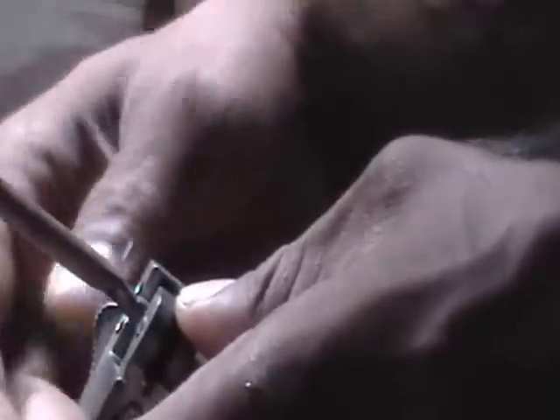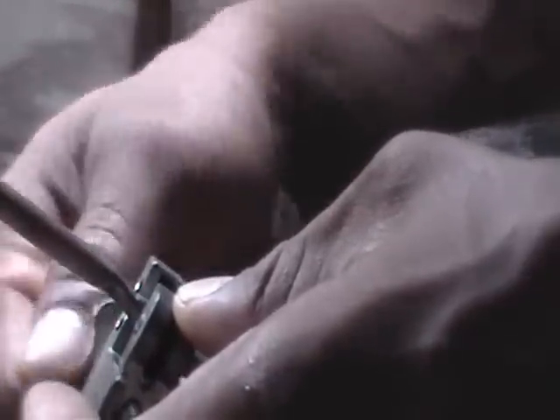The first order of the day is to cut this pipe right at that kink. I have my tube cutter — I'm going to place it around the line. You just want to grip it just slightly. As you turn, you just tighten. What is happening is this blade is just going deeper and deeper in — as I tighten and I turn, it's sinking deeper and deeper into the copper. This is soft copper — remember, these tubes for refrigeration use soft copper.